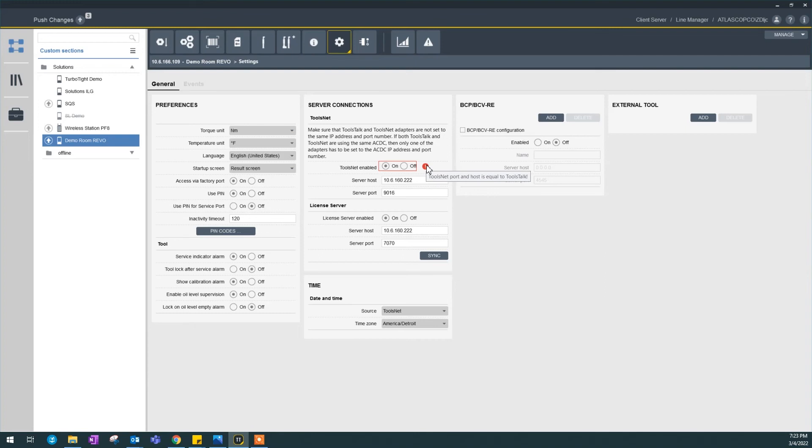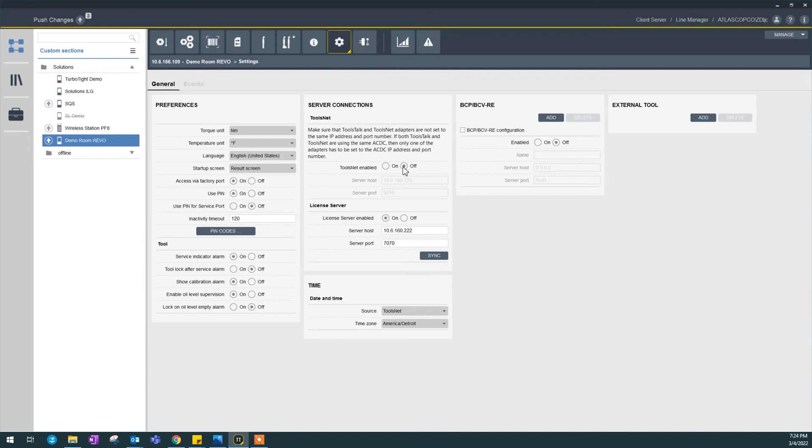There will be a warning, say ToolsNet port and host is equal to ToolsTalk. If we really push this configuration, this controller will be kicked off because you're reporting to the same port and same IP address, so the connection will clash. So I'm going to turn this off.